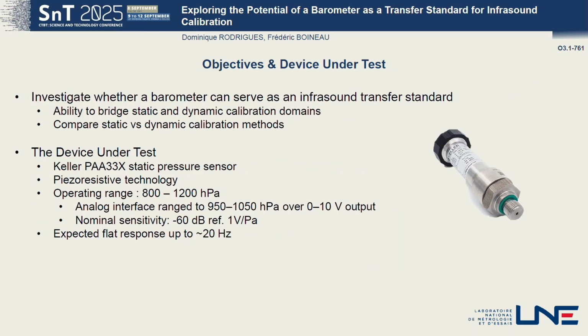The basic idea is to explore how a barometer, with its ability to bridge the static and the dynamic calibration domain, can be used as a dual calibration device to establish such a reliable transfer standard. Here we tested a barometer, a Keller PAA-33X, which uses piezoresistive technology, in the following operating range. One interesting option of this sensor is that we have the possibility to scale, to range its analog interface to a smaller range to fit better to the infrasound operating range.